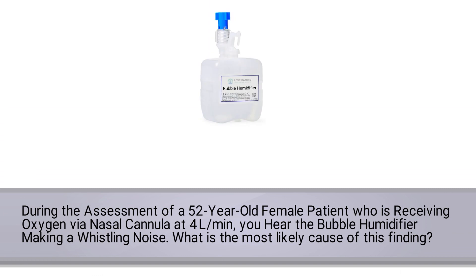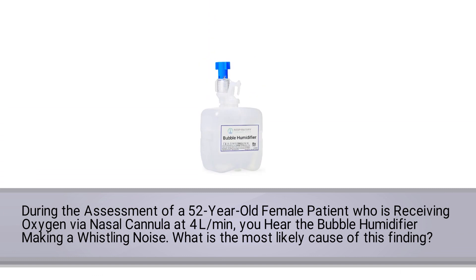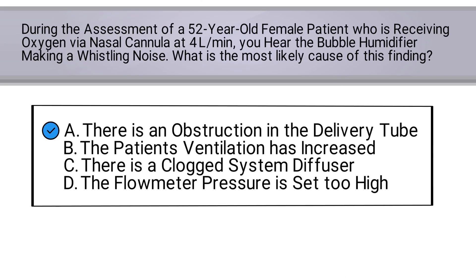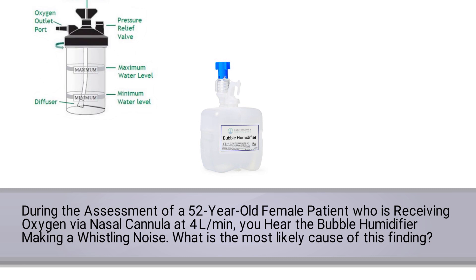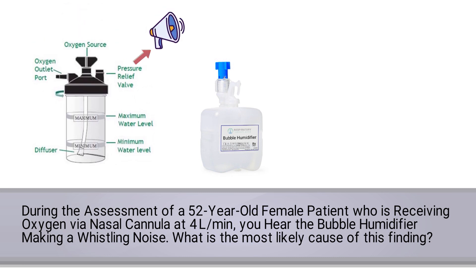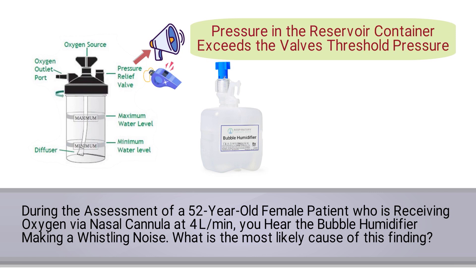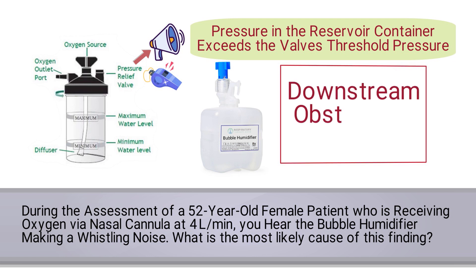If you've ever accidentally stepped on the tubing of a bubble humidifier while it's being used, you will automatically recognize that the correct answer is A. The relief valve of a bubble humidifier was designed to sound whenever the pressure in the reservoir container exceeds the valve's threshold pressure, resulting in a loud whistling noise. The most common reason for this to occur is when there is a downstream obstruction to outflow.